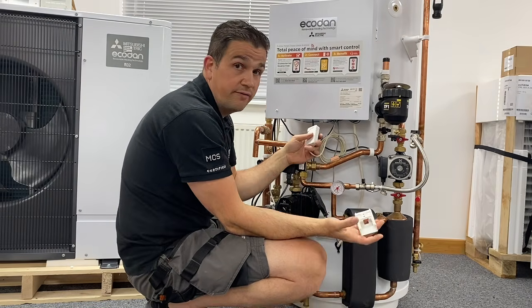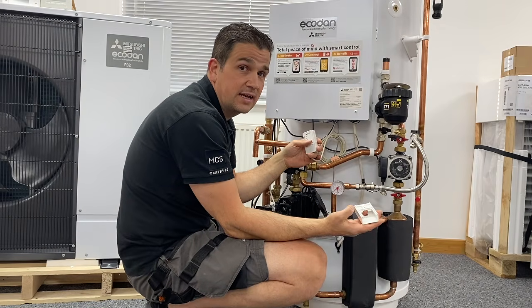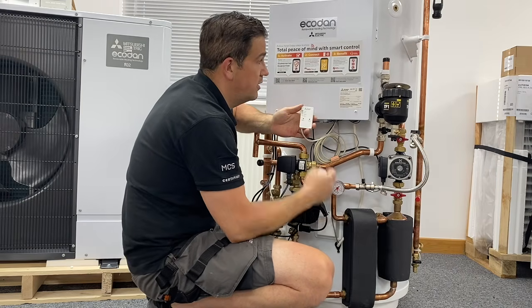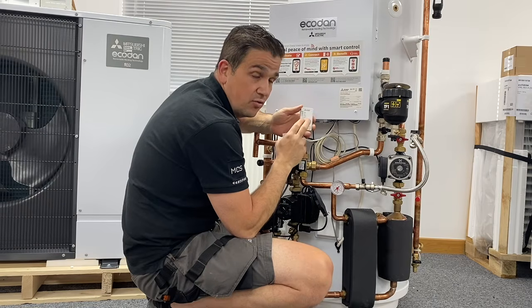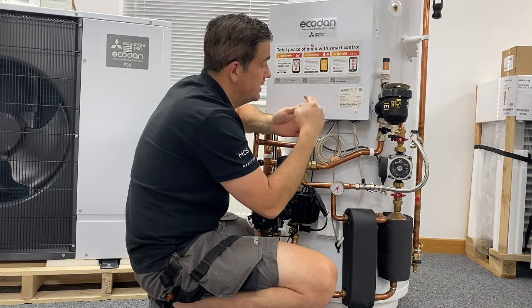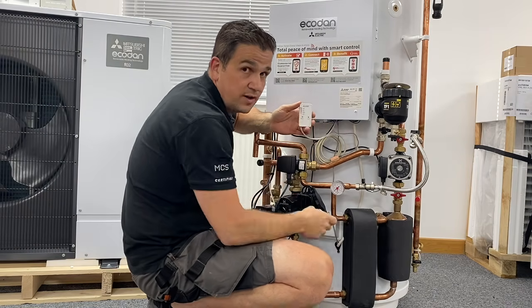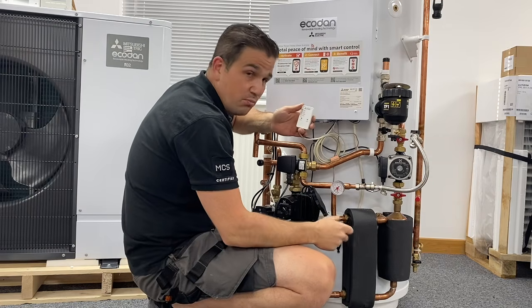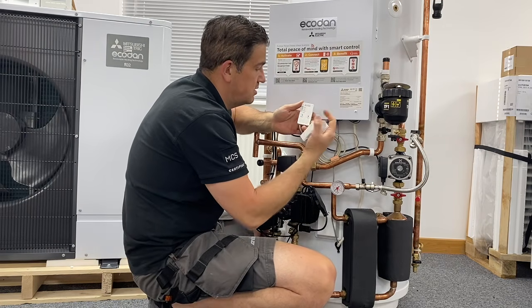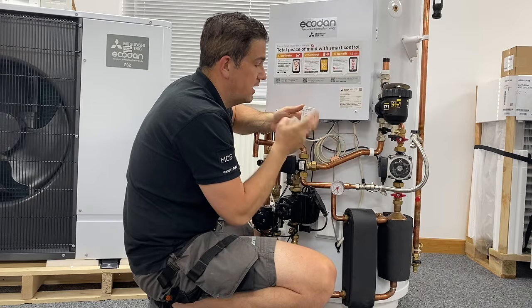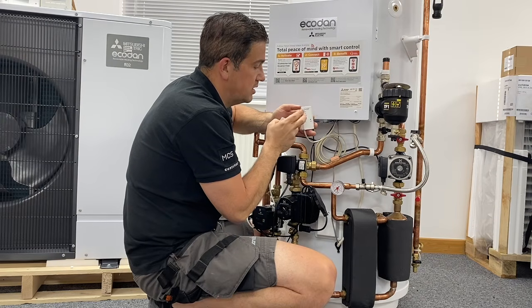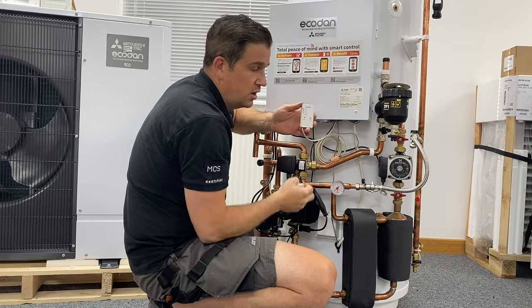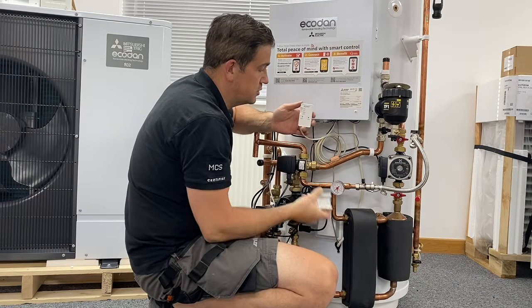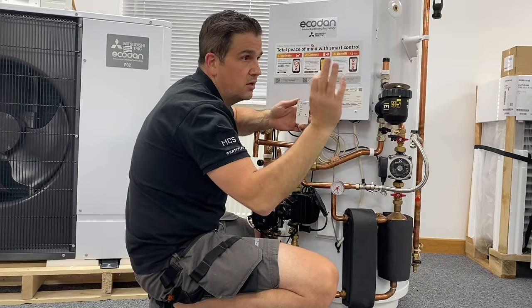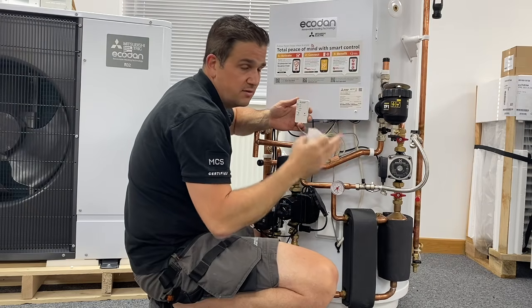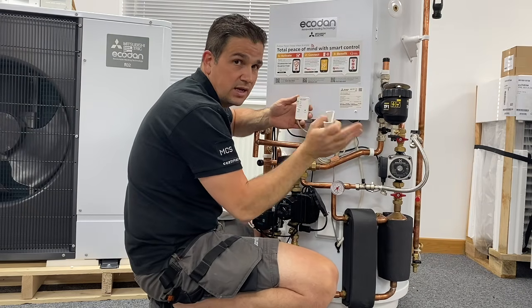I mentioned Wi-Fi, using an internet connection. Well, this is installed on the heat pump. You just do the connections from the interface to your Wi-Fi signal, and it can be done very simply. You've got a mode button, you hold it in for a few seconds, and you start getting a number of lights coming in sequence, which would be explained by your installer. Then you go to your router. You can WPS the system or press a button, and it will quickly pair.